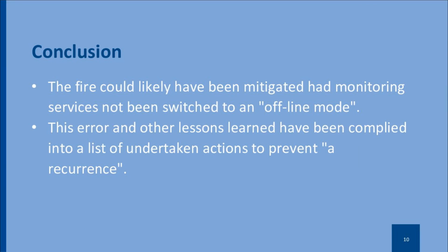I will shift across. As you can see, the report showed that the ignition of the fire from the coolant leak should have been made known to the system operators had the monitoring services been switched on. But as they were in commissioning, they were switched to offline mode as they moved from megapack to megapack. So that's another learning curve from this fire: you should make sure there is no offline monitoring at any point, because a thermal runaway event could ignite, and if you don't catch it early, you could be in trouble.